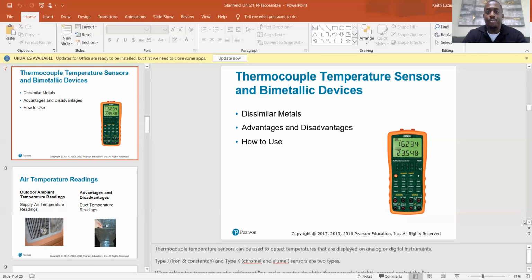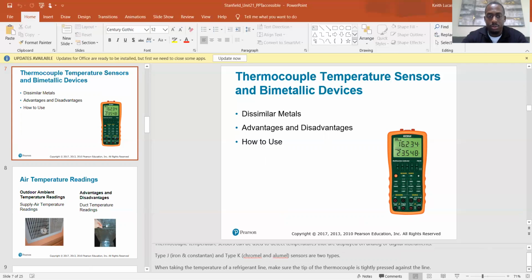Thermocouple temperature sensors and bimetallic devices. So thermocouples are made of dissimilar metals that are connected at the ends. Advantages and disadvantages and how to use them. So thermocouple temperature sensors can be used to detect temperatures that are displayed on analog or digital instruments. Type J, iron and Constantan, I probably butchered that word, and type K, chromel and alumel sensors are two types. The K type, I believe, are the ones that we use the most, or the ones that I have.